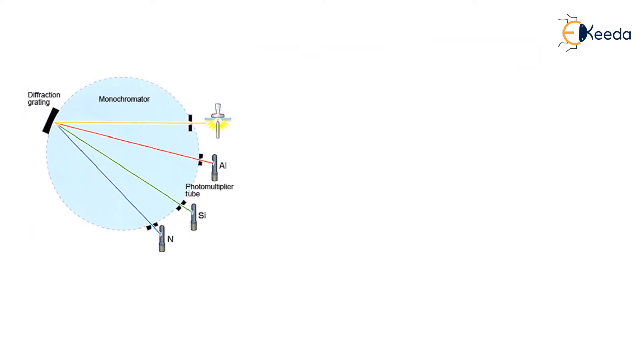Here they are showing a monochromator with diffraction grating. First, a discharge plasma is created; that discharge plasma emits a spectrum; that spectrum is passed through a diffraction grating; after the diffraction grating, the emission passes through the photomultiplier tubes, through which we determine which element is present or absent, and how much quantity of each element is present.